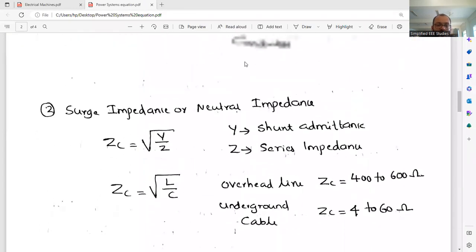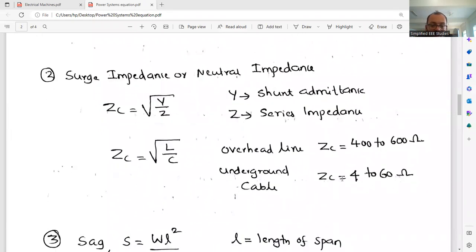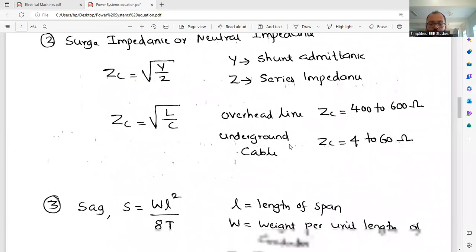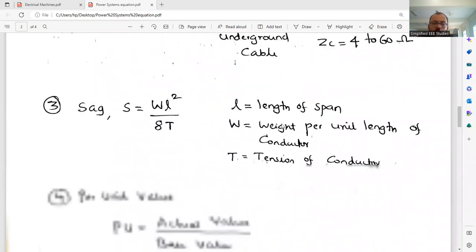Similarly, surge impedance, which you can also call characteristic impedance. You can use any of the formulas. If inductance and capacitance are given directly, ZC can be calculated using the square root of L by C. If the shunt admittance and series impedance are directly given, use the formula ZC is equal to square root of Y by Z. This is very important, kindly make a note of it. For an overhead line, the surge impedance varies from 400 to 600 ohm, whereas for an underground cable, the surge impedance varies from 40 to 60 ohm. Surge impedance is more in the case of an overhead line.